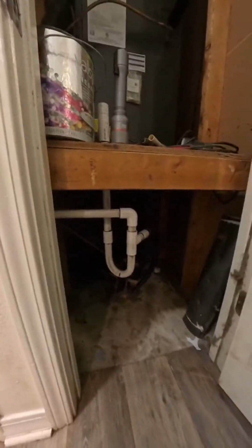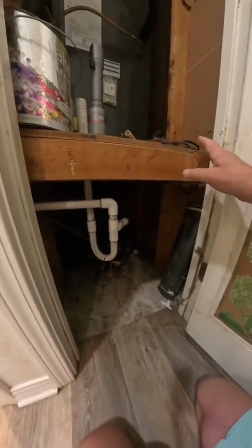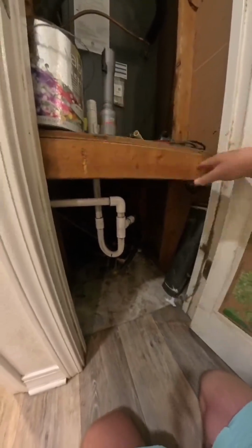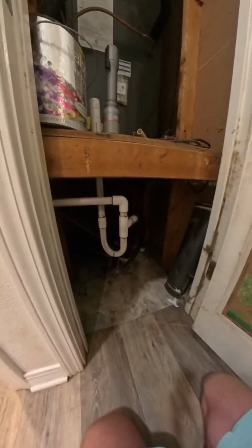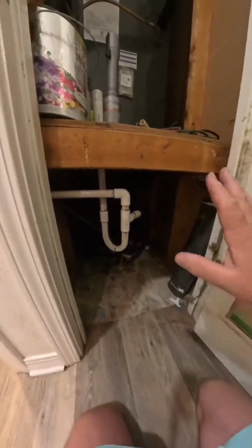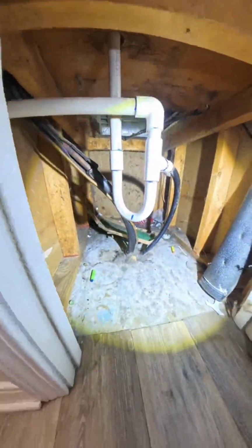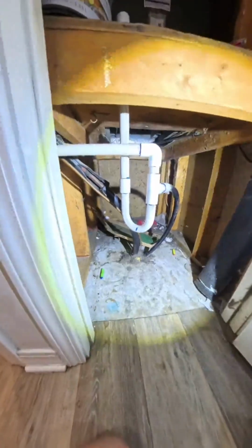So this is a dumb design. It's always a dumb design. It's never a good idea. Why do you have so many openings? Why don't you just block this off? Just block it off. Do yourself a favor. Seal it up. Put your filter grill in here or something. You could still have your door with your louvers, whatever you want, but your filter needs to be sealed. The air coming in needs to be sealed. The dog hair doesn't need to be rattling around down here doing whatever it wants to do like this is some kind of kennel club. We're better than this.